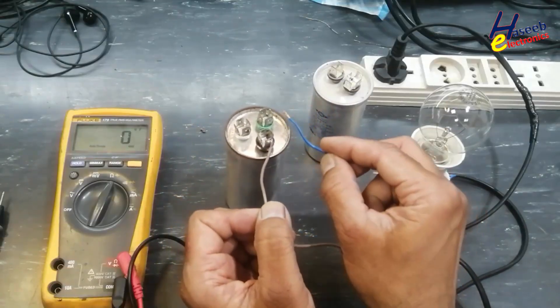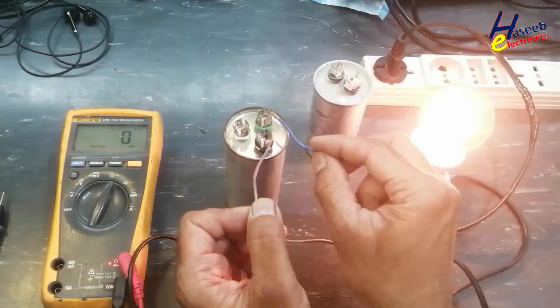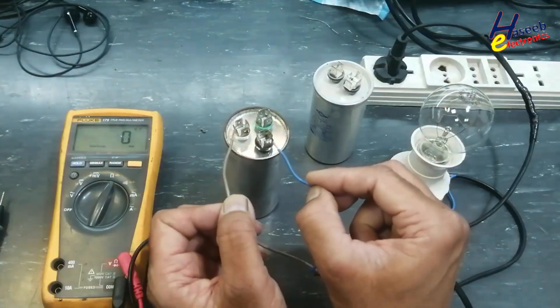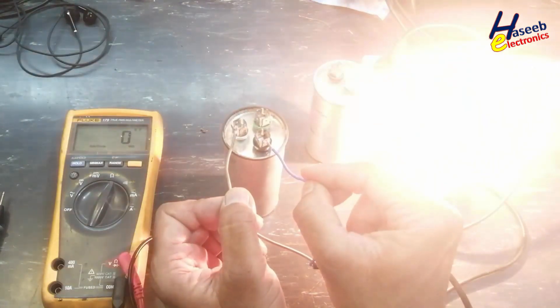Common with fan capacitor: dim indication. Common with compressor: full bright. So this capacitor is good.